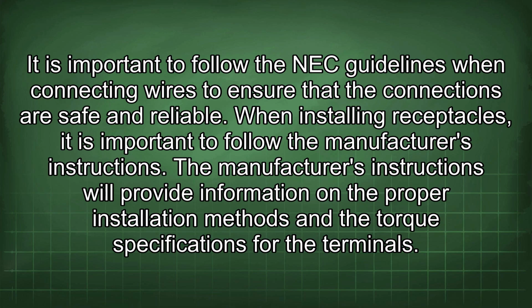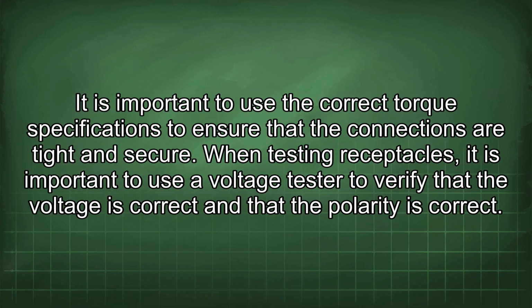When installing receptacles, it is important to follow the manufacturer's instructions. The manufacturer's instructions will provide information on the proper installation methods and the torque specifications for the terminals. It is important to use the correct torque specifications to ensure that the connections are tight and secure.